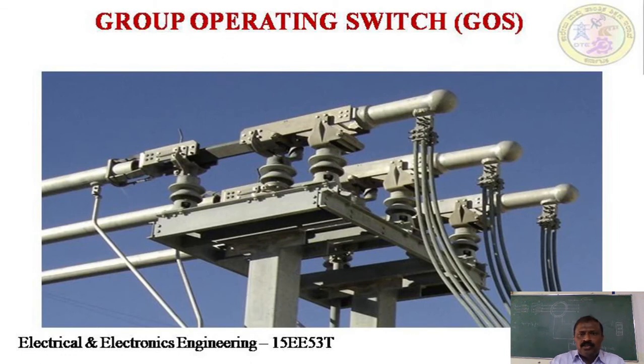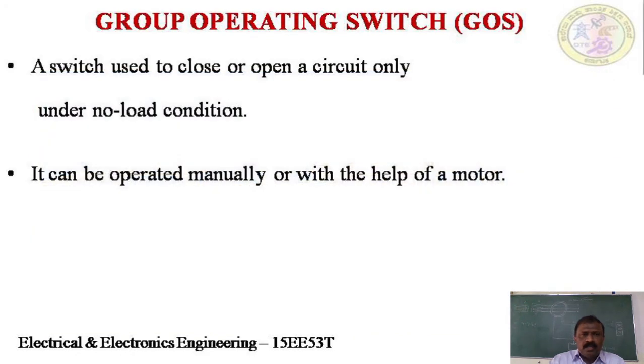This is the actual picture of the GOS, or group operating switch, popularly known as GOS. The GOS can be defined as a switch used to close or open a circuit only under no load conditions. This acts as a switch which can be closed or opened only during no load conditions. The GOS can be operated either manually or with the help of a motor, which is called a motorized GOS.